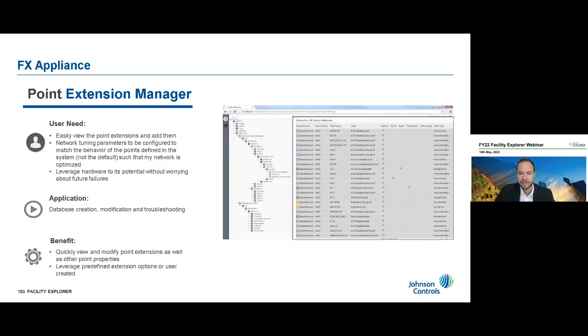Next is the Point Extension Manager, centered around the user need to easily view and add point extensions and configure tuning policies to optimize the network in a simple, quick way. It builds a table view, as shown on the right-hand side, for all the imported points, letting us quickly check and uncheck points to add and remove extensions like trends, alarms, and totalization just by checking the point.